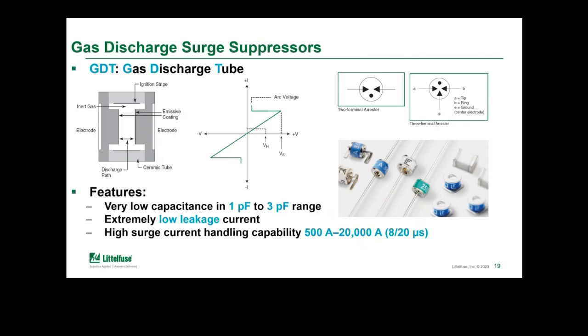And then as the transient dissipates and the current drops below a given value, the arc will suddenly stop and the event will extinguish, and then the device will go back to a high voltage condition and low leakage current. These devices, as I mentioned, can handle fairly high currents, anywhere from about 500 amps to about 20,000 amps for a typical 8x20 waveform. Key features are they have very low leakage and very low capacitance.